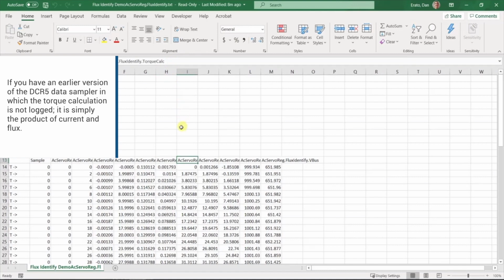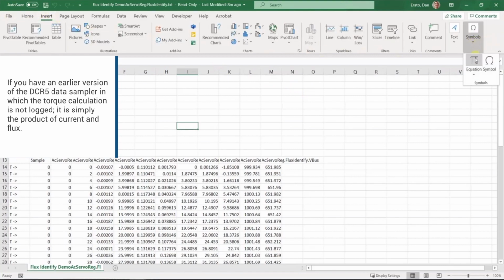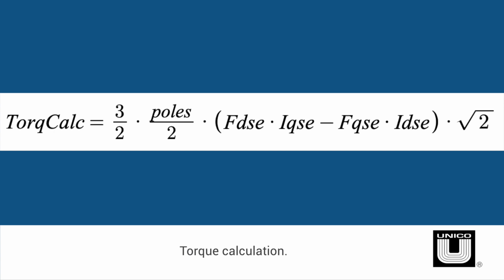If you have an earlier version of the DCR5 data sampler in which the torque calculation is not logged, it is simply the product of current and flux. More specifically, the torque calculation equals 3/2 times the pole pairs times the difference of D-axis flux times Q-axis current and Q-axis flux times D-axis current. Since the current feedback is logged in units of amps RMS, we need to multiply by the square root of 2 to convert to units of amps peak. The units of the torque calculation are in Newton meters.